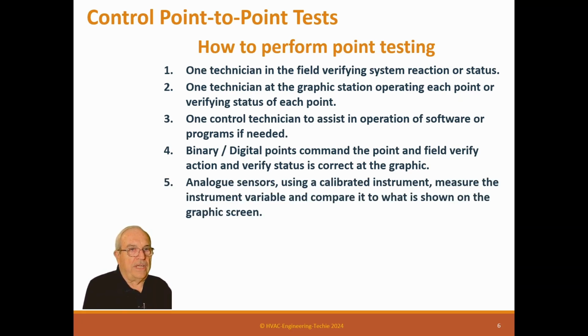Analog sensors: using a calibrated instrument, measure the instrument variable and compare it to what is shown on the diagram. Now also, backing up to binary points, since most systems have status on the computer, we'll ask the guy to start that machine up. He starts it up, then we'll ask him to verify the status is running. And if it is, then you've checked 2 points. You started the start-stop point and you've checked the status point. For an analog sensor, you do what we just said: use a calibrated instrument, measure the instrument variable, and compare it to what's shown on the graphic screen.